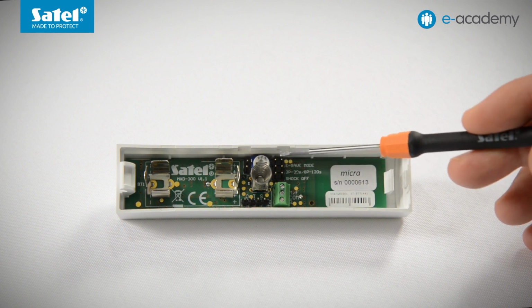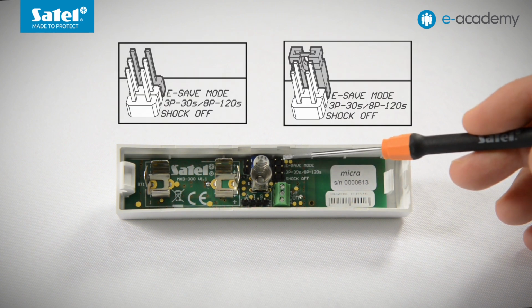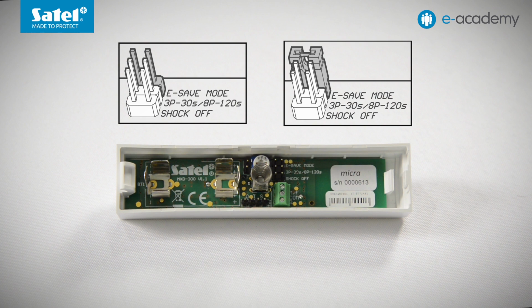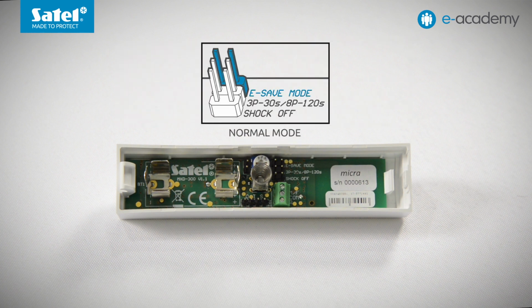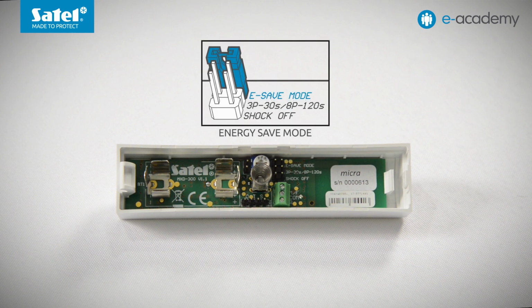The first of the 3 pairs of pins, designated as E-Save mode, controls the detector operating mode, normal or energy saving. When the jumper is removed, the detector will work in normal mode, that is, any alarm will result in a radio transmission. When the jumper is placed over the pins, energy save mode is enabled. In this case, information on alarms is sent no more than once every 3 minutes. The exception are tamper alarms. Information on tamper is sent each time.